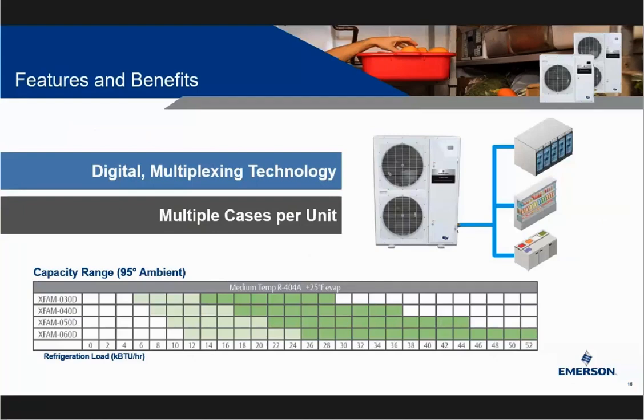The Digital X-Line gives us this multiplexing technology option, which is unique, as we've talked about, that enables us to tie into multiple cases per unit. In this little picture we have here, we have one Digital X-Line tied to a walk-in cooler, a display case, and a food prep station. There can be a variety of different applications this ties to, but that helps give a visual for what this looks like. Down at the bottom, we actually have a list of the different condensing units we've released. So we have a 3, 4, 5, and 6 horsepower Digital X-Line offering, and that's at fully loaded capacity. You can see here in the chart that there's a green, light green, and a dark green area. Hopefully that light green is showing up well for you on your screen.